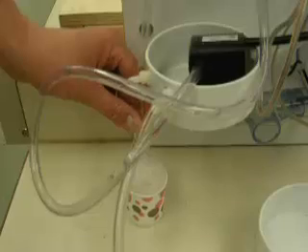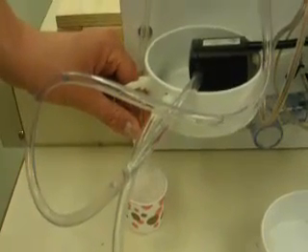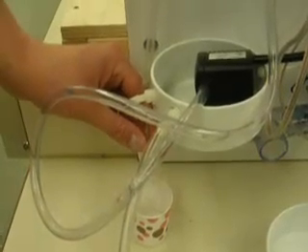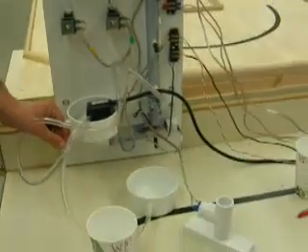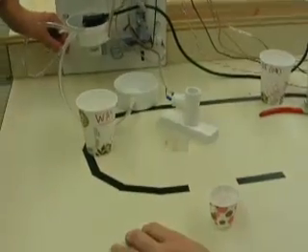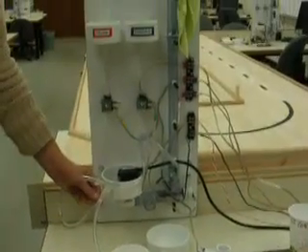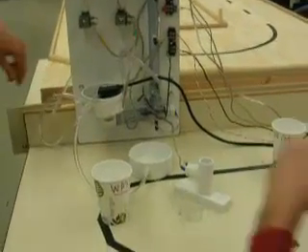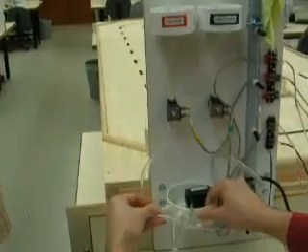Let's get a look at the valve running. You want to run some water through it before you do your test because otherwise the bubbles might get caught in there. There's a little water running through, so I'll pause that. Now you would want to empty the tank and then run it for one second or two seconds or five seconds. Here I'm going to do one example. I'm going to run it for three seconds and see how much water we captured. 1,001, 1,002, 1,003. Of course, you should do that more precisely with a stopwatch, but you can then measure the volume of the water that's captured, and that will give you the flow rate.